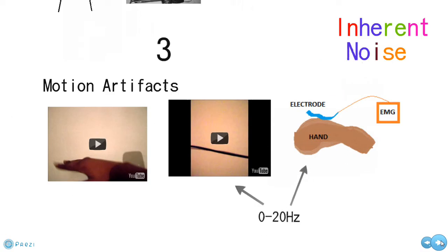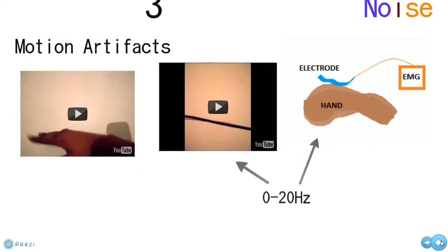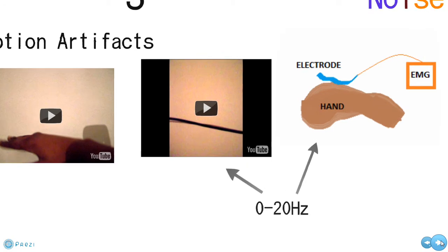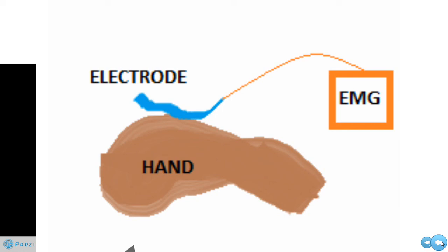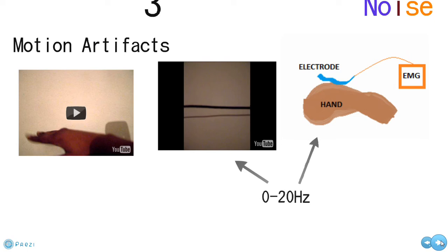Motion artifacts can also generate unwanted signal. This can be due to the electrode and skin contact, a phenomenon known as impedance, or wire movement. Both impedance and wire movement are in the region of 0 to 20 hertz. In a slightly subtler way, motion artifacts can be caused by a patient moving during a recording.